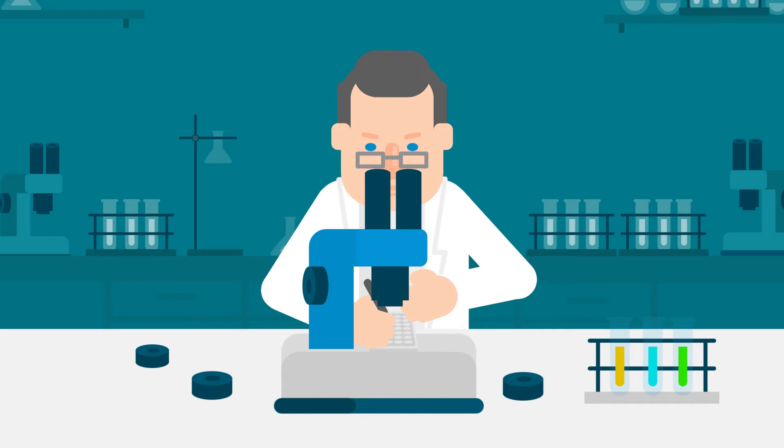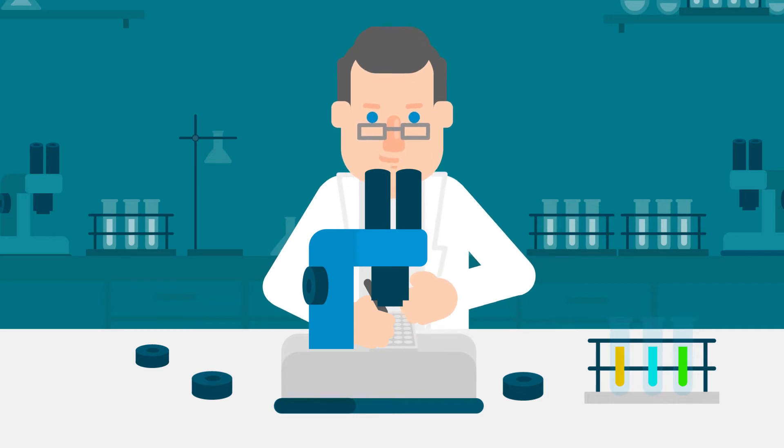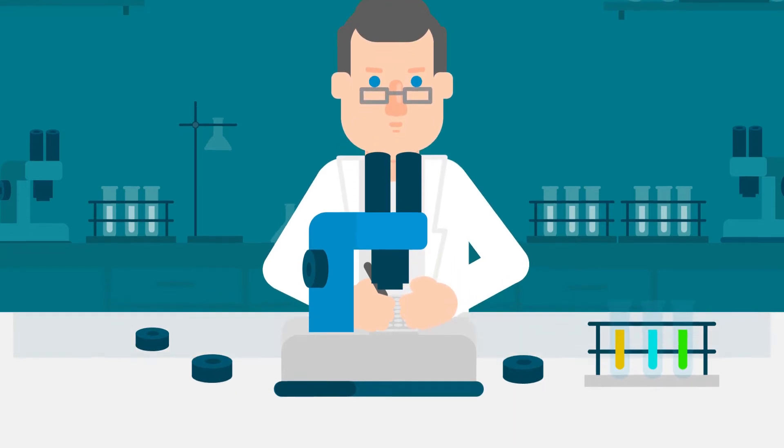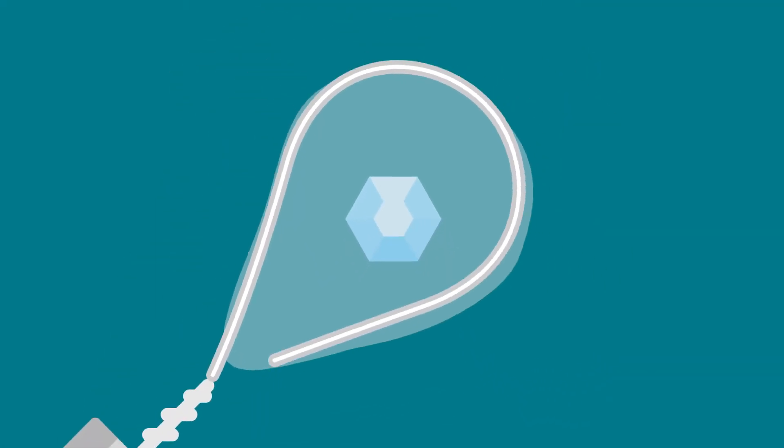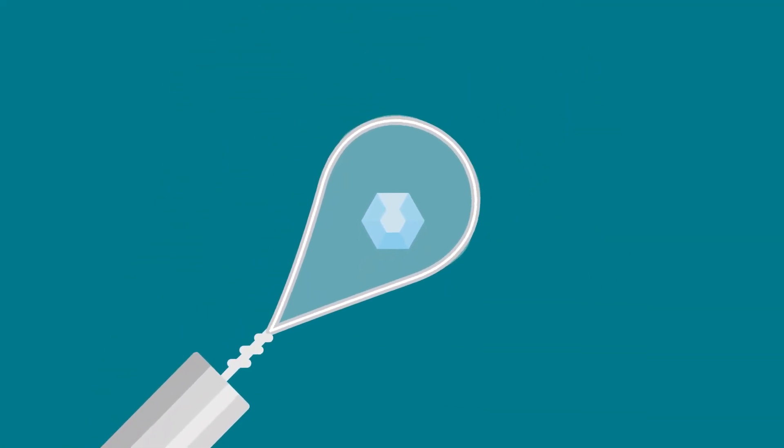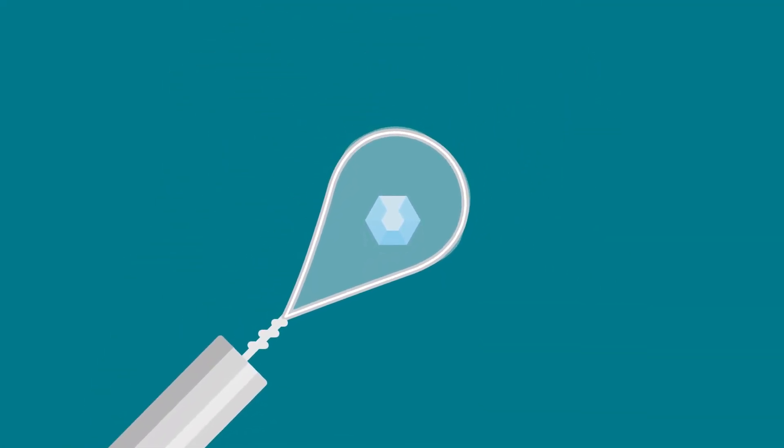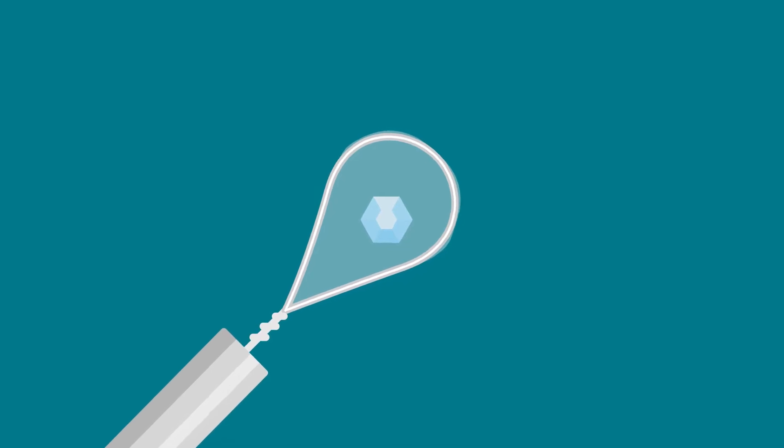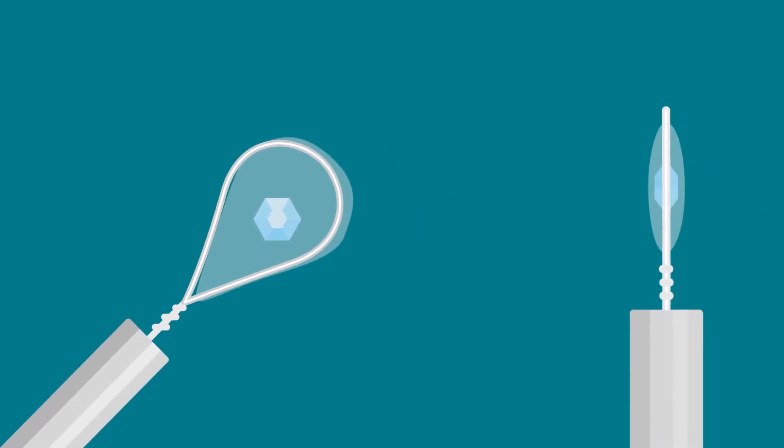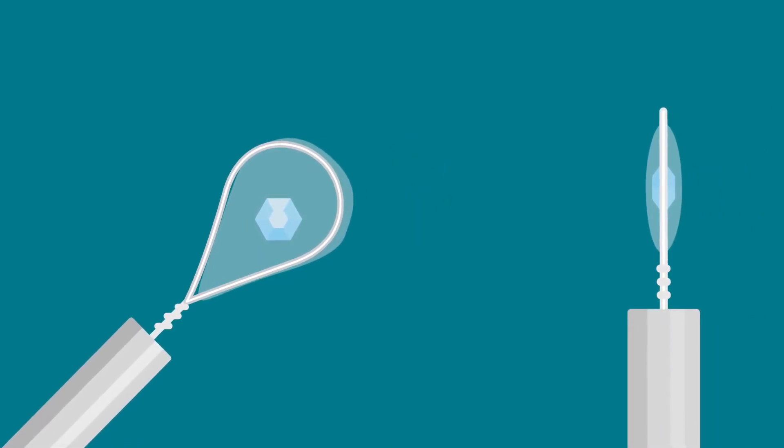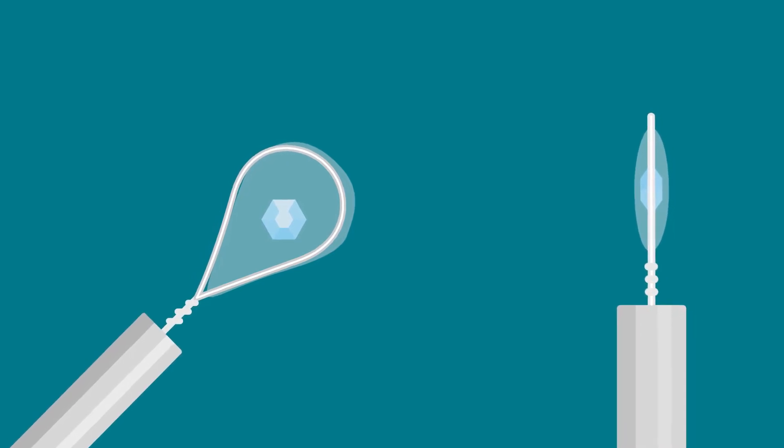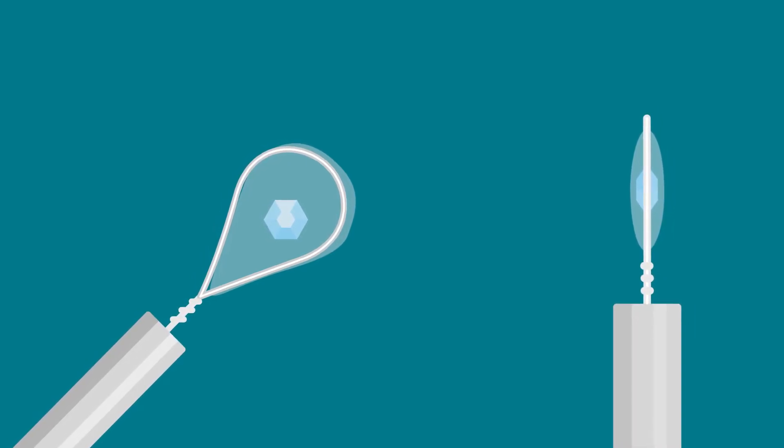Older loop designs allow crystals to be retrieved from drops but have drawbacks that can impact results. First, older loops are made from non-X-ray transparent materials. Crystals are often mounted suspended within a large drop of fluid in the loop, such that the loop material itself can be kept out of the X-ray beam.